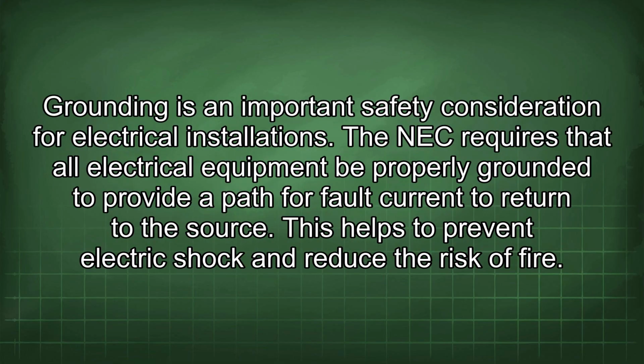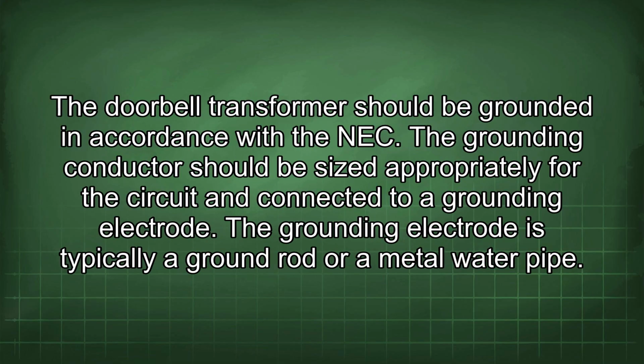Grounding is an important safety consideration for electrical installations. The NEC requires that all electrical equipment be properly grounded to provide a path for fault current to return to the source. This helps to prevent electric shock and reduce the risk of fire. The doorbell transformer should be grounded in accordance with the NEC. The grounding conductor should be sized appropriately for the circuit and connected to a grounding electrode. The grounding electrode is typically a ground rod or a metal water pipe.